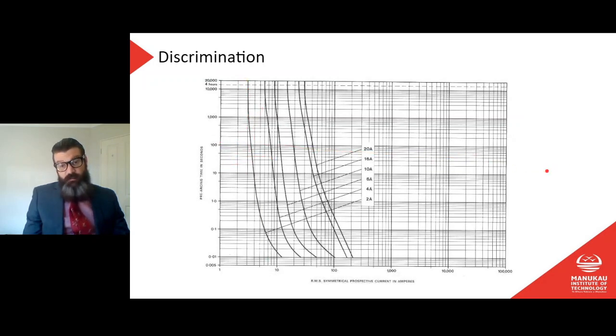So that's pretty good. That's a pretty good current characteristic or time characteristic curve. Should be pretty steep going downwards. If it's mostly horizontal, that means that with a large increase in current, we're not seeing much of a reduction in time. So more vertical is better than more horizontal in this case.